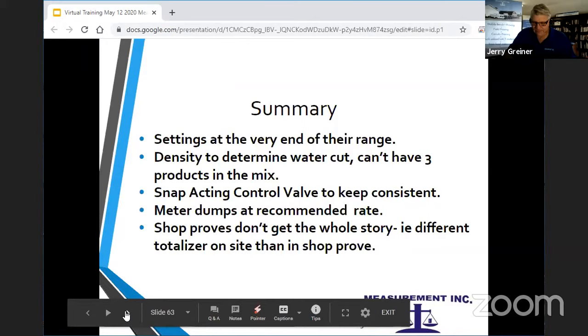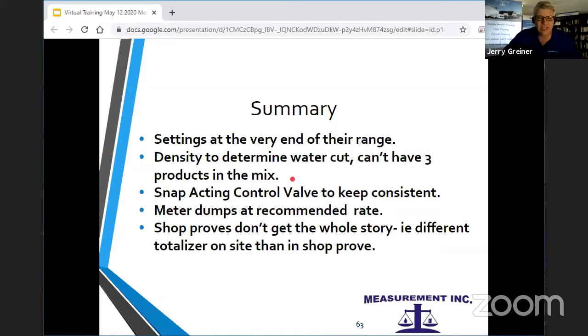Got some of the things that we've learned so far out of this today. Settings at the very end of their range: if you have a setting that goes from 0 to 8% and you're at 8%, question the settings that are right at the very end of the range. There's often errors, because where we had a 0 to 8%, it should have really been 10%, but the range didn't go high enough.